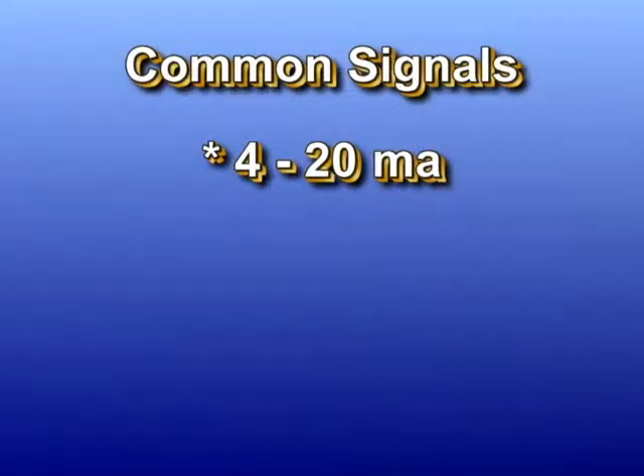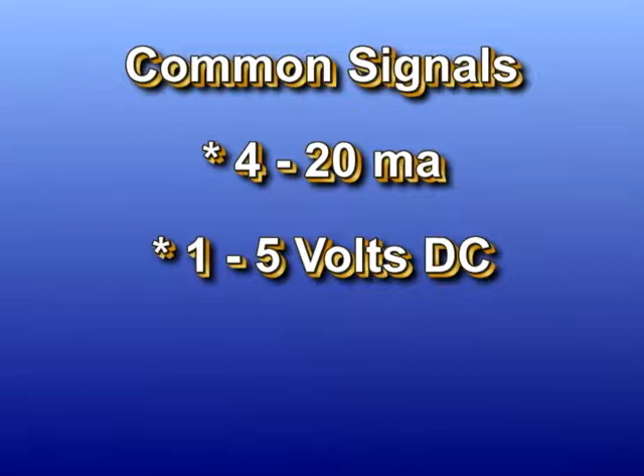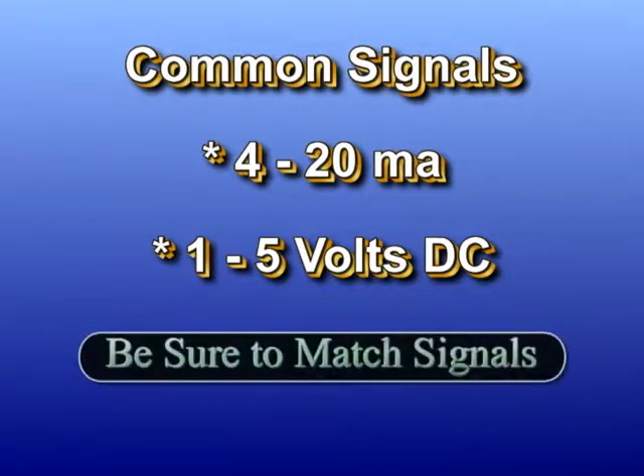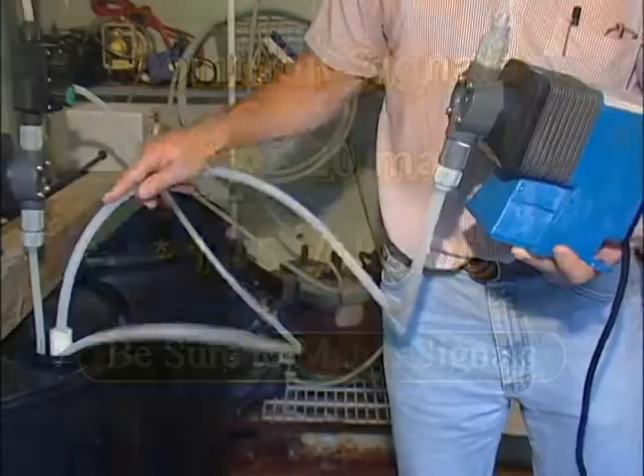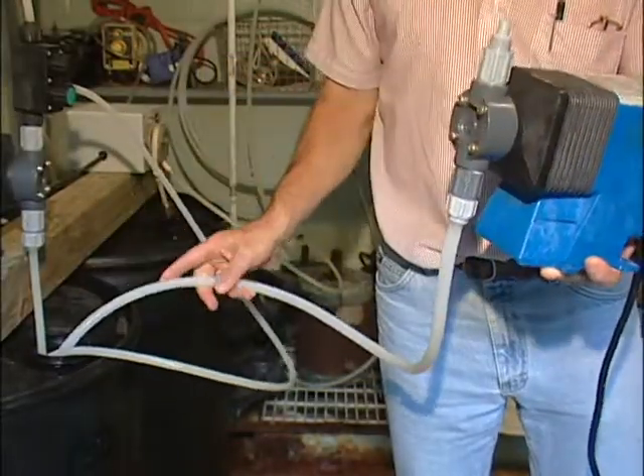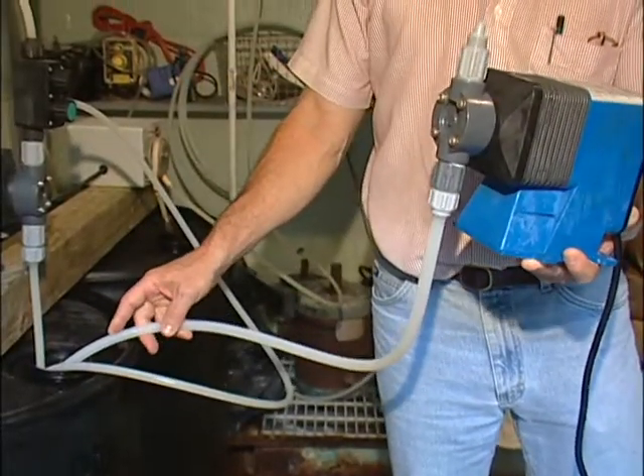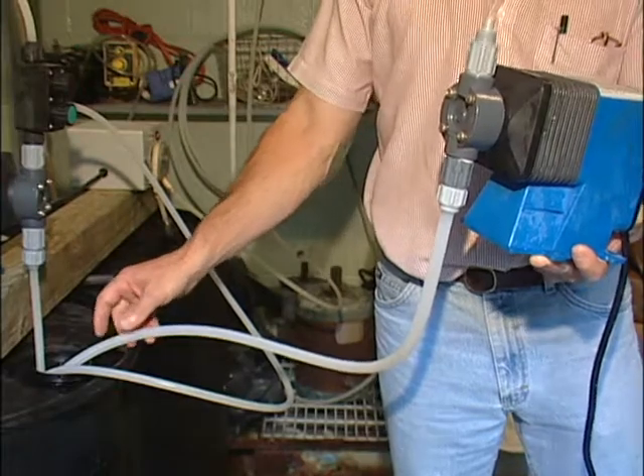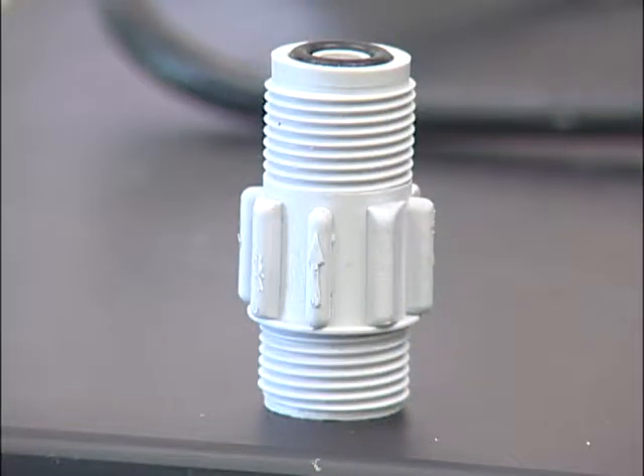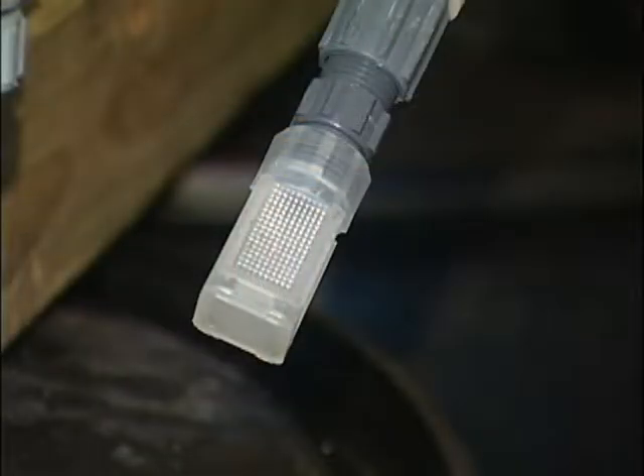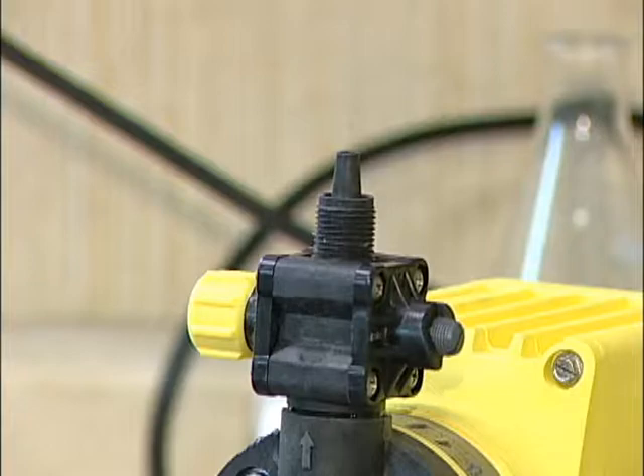Some pumps can be programmed to respond to signals set in a prescribed range. Some pumps run off a 4 to 20 milliamp signal, while others respond to a DC current of 1 to 5 volts. Operators should be careful to match the signals from the sensors to the pumps. Other essential pieces of equipment are check valves, foot valves, and four-way valves.